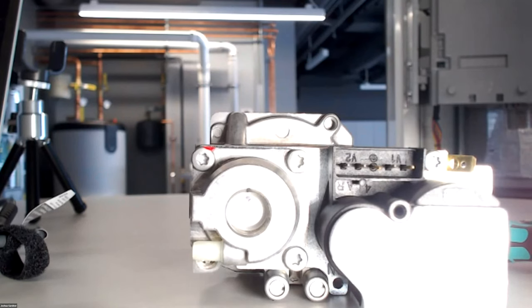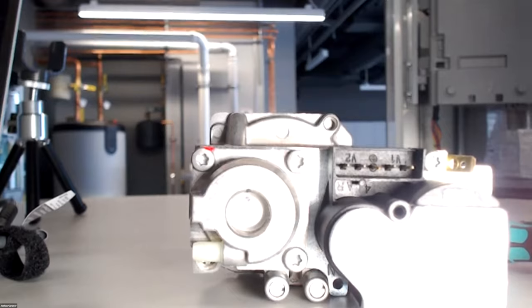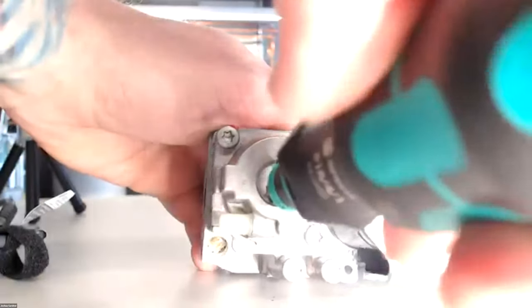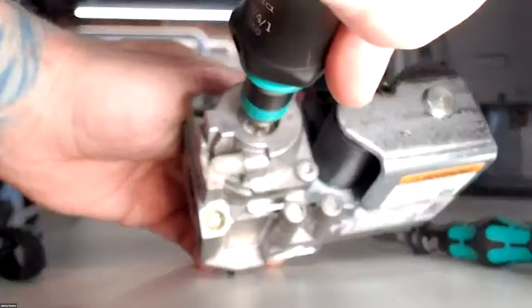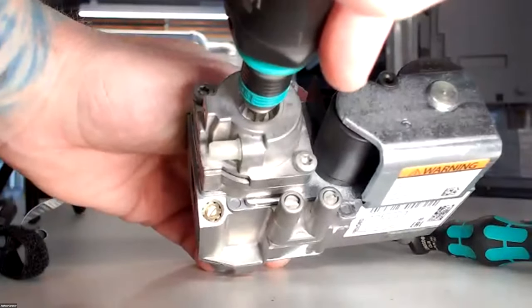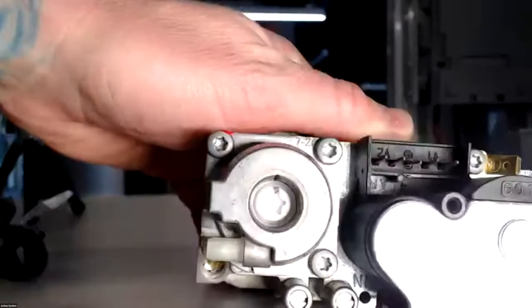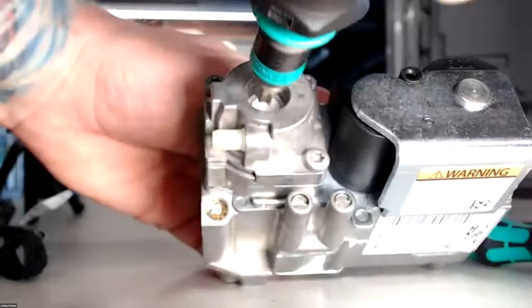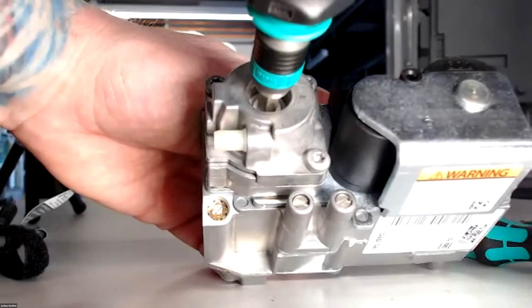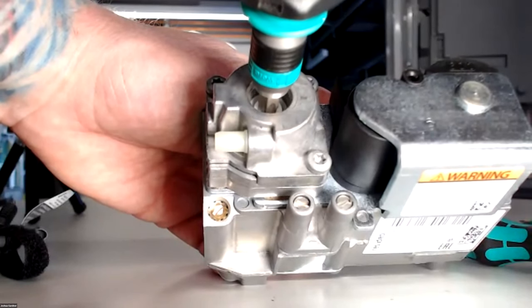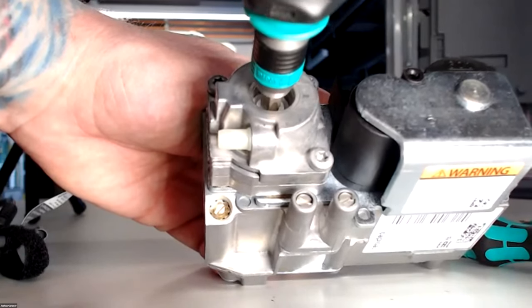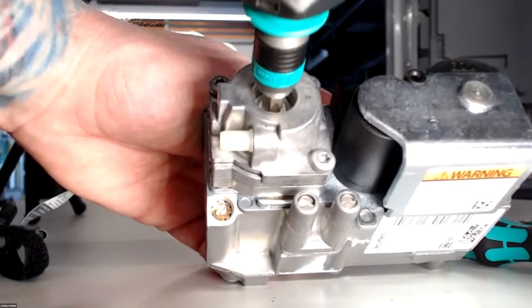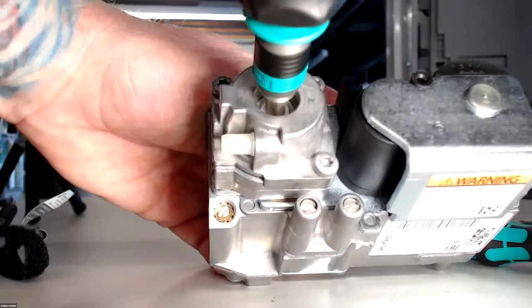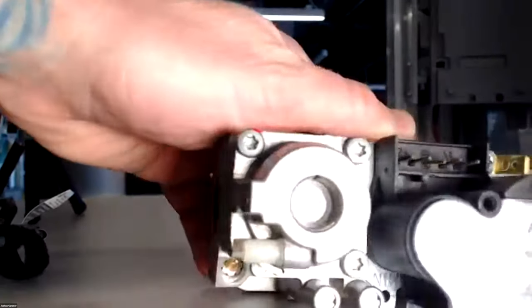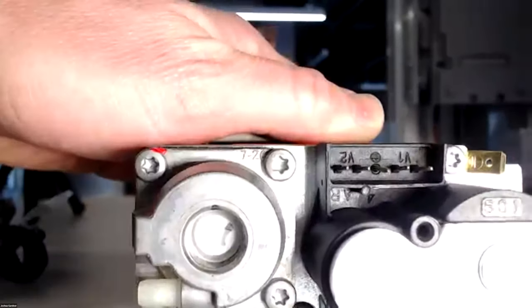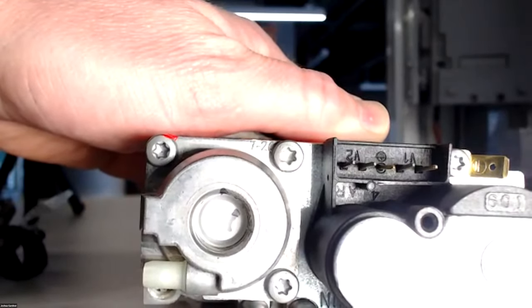So we're going to have it in low fire, running. And I'm going to take this and turn it very slow, about that far. Looks like almost nothing. If it's not there, I'm going to turn it clockwise. And this is in the instructions: you increase your gas pressure by turning it clockwise, decrease it counterclockwise. That's the most I've ever had to turn one of those, about a quarter turn.